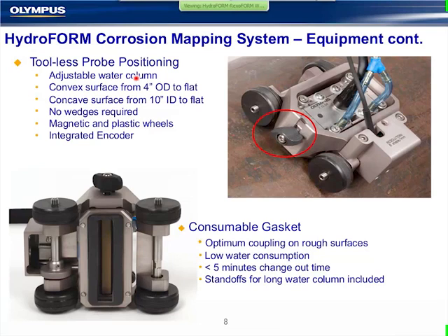There's an adjustable water column that you see here. As the diameter of the pipe is changed, the probe can be articulated. One side fixed will keep the probe parallel to the pipe surface. And we'll also explain a synchronization on echo feature that allows this to be very efficient for data sizing. This can perform inspections on a convex surface from 4-inch ODs to flat, or an internal inspection on a concave surface from 10-inch IDs to flat.